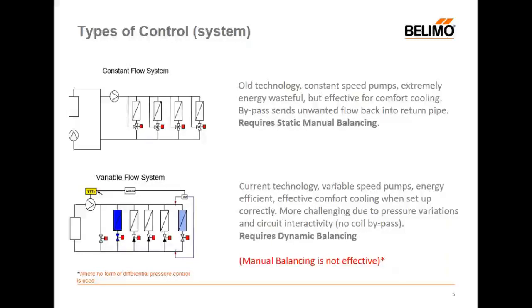And so we move now to current technology, which is signified by variable flow systems, where variable frequency drives integrated into pumps is now quite common. We probably see this in 90 to 95% of systems, thankfully. And that's a really good thing because we can better match supply with demand. But the issue really for the control elements is that we can't have our bypass because we rely on the rising pressures caused by closing valves to signal the pump to slow down to match the new normal, which is a reduced demand. And the reduced demand is signified by an increase in pressure. And we won't have that increase in pressure if we have a bypass.